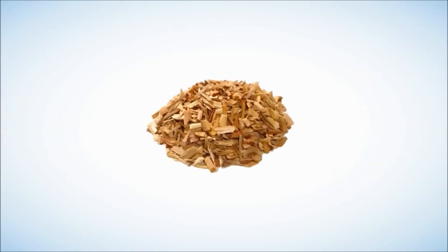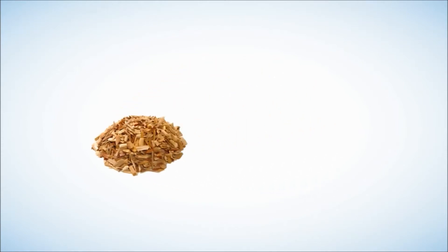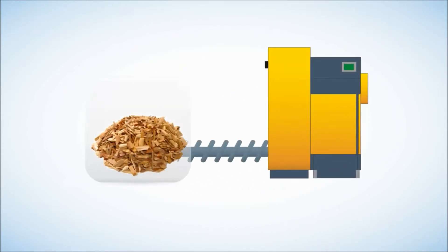Wood chip is timber that has been shredded in a chipper. Like wood pellets, it is an easy fuel for automation with a screw feed taking the chips straight from the store into the boiler. Chip systems are inexpensive to run, although initial capital outlay is greater than other technologies due to the additional parts required to make the boiler fully automated.